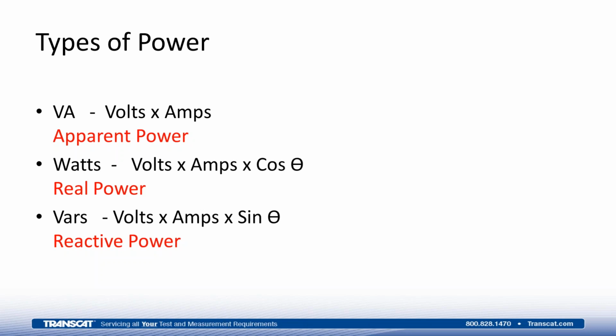By way of example, if we had an incandescent bulb, which is a purely resistive load, theta would be 0, and the cosine of 0 is 1. We would have 1 times amps times volts, and as a result, we would wind up with VA and watts being equal. Now, VARs are the hardest one to describe in the industry. They're the portion of the system that we call reactive power, and the reactive power is almost the opposite of the real power. This is the part that doesn't do any work, but has to be present in order for the work to be done.